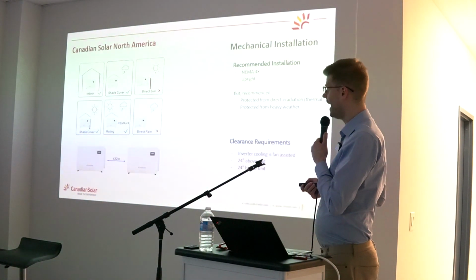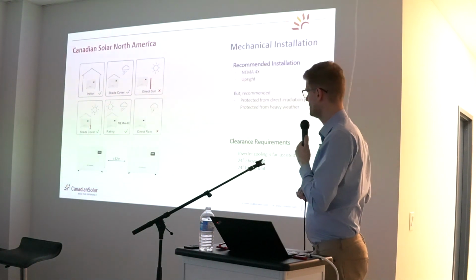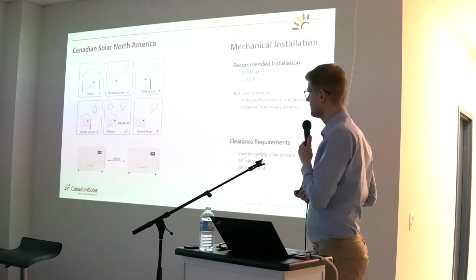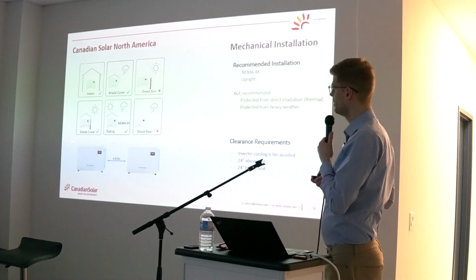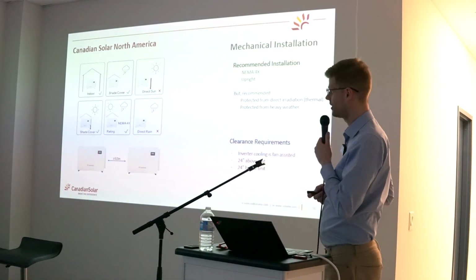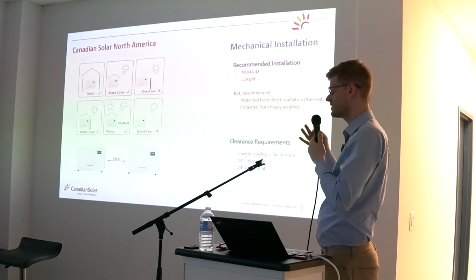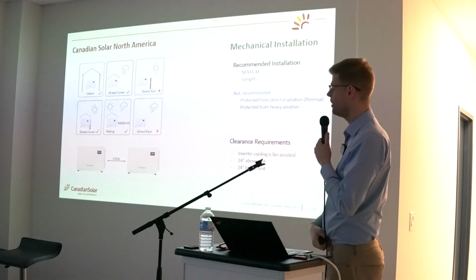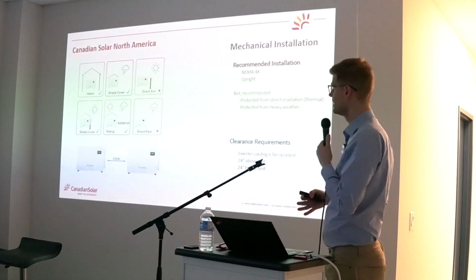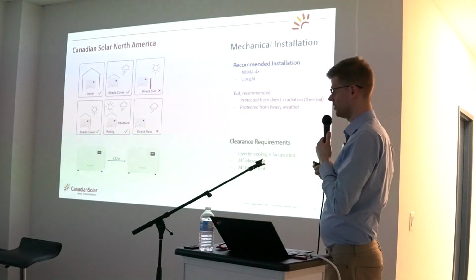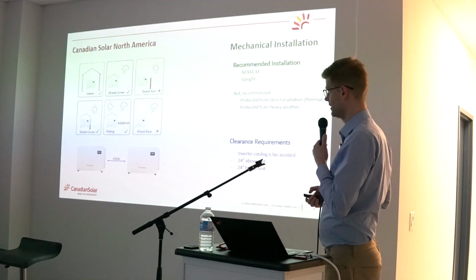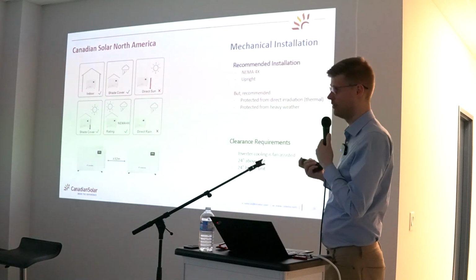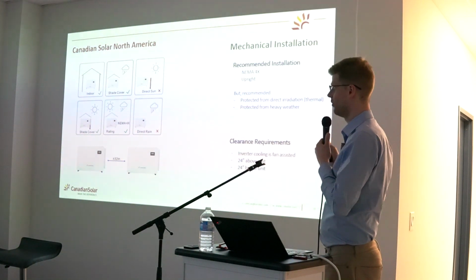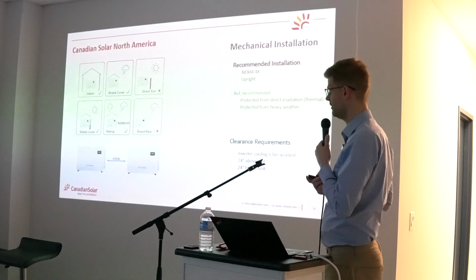How it should be and can be installed in the Canadian market, that's just a screenshot from the manual. You have a few recommendations that is perfect. So of course you can install it indoors. That's always the best case scenario for any power electronic. You want to have it protected. But you can also install that, and that's the most common scenario in Canada, directly on the roof. And we talk about a little bit later why that is the most common and the most effective way of doing it.